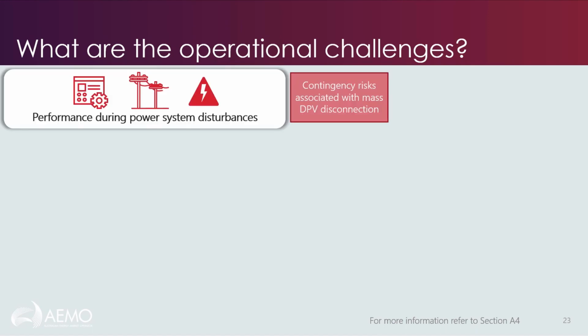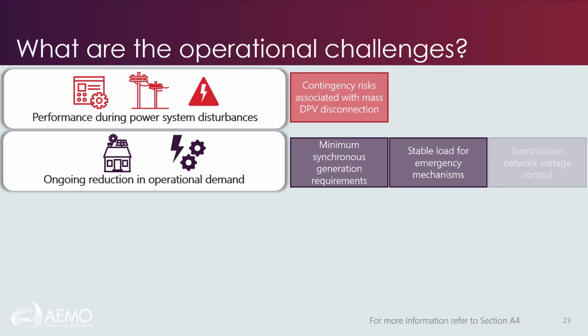So what are the operational challenges that DPV is having on the power system? The first impact is the response of DPV during a power system disturbance. With penetrations of DPV, we need to understand how they respond to events such as sudden fluctuations in voltages. As DPV grows, their aggregate response becomes more apparent, and therefore understanding their response becomes more critical. Knowing whether DPV disconnects following events helps to determine the potential contingency size if mass DPV was to disconnect in concert following an event.